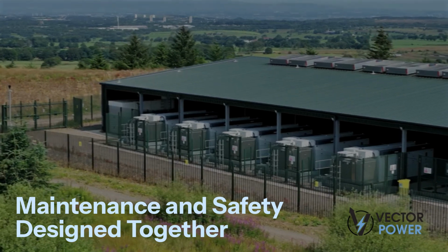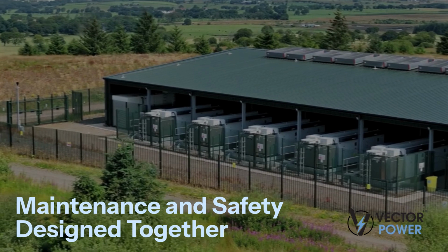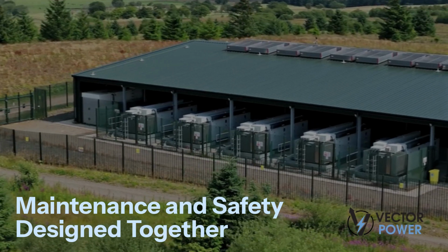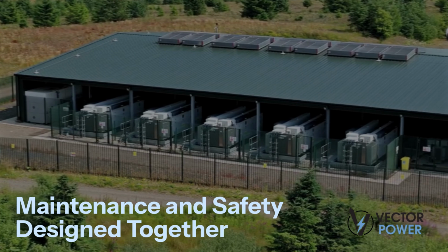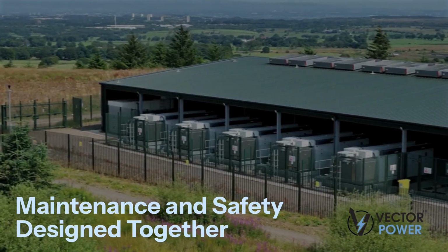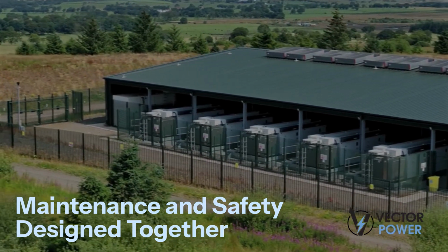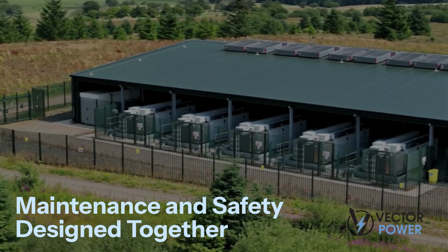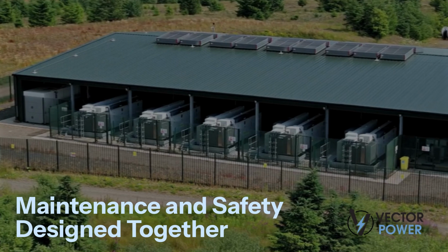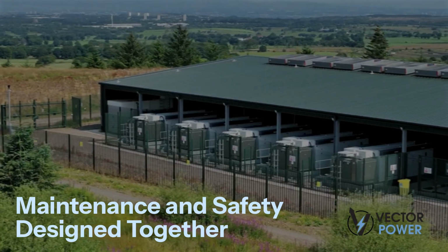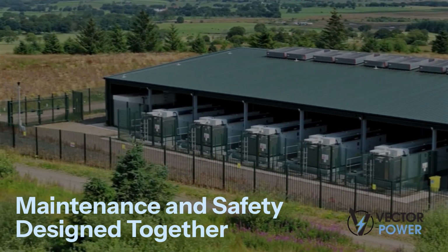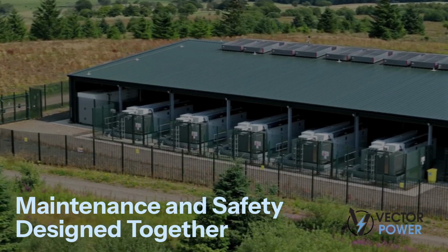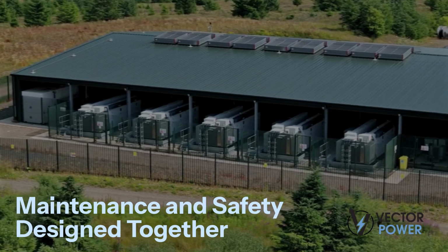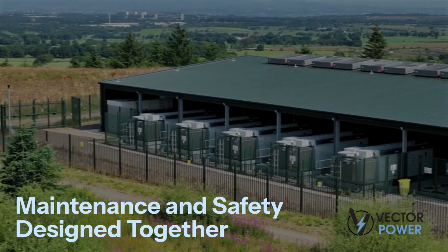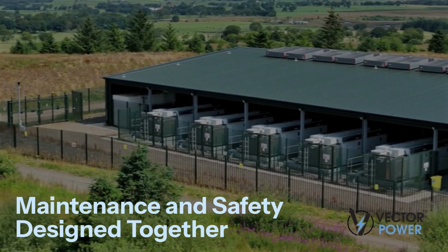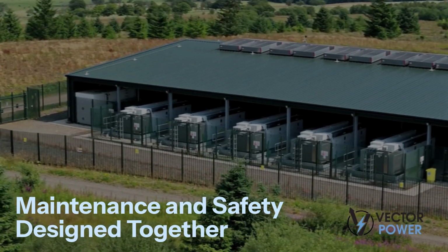Historically, battery maintenance was often treated as a narrow reliability function, for example, keep the UPS batteries alive. In modern battery energy storage systems, maintenance and safety are inseparable. Poor maintenance, such as disabled fans, loose terminations, and outdated firmware, escalates safety risk. Inadequate safety controls, like missing lockout tagout or no gas detection, expose workers during routine maintenance. Changes made during repairs can inadvertently break system level safety certification, for example, UL 9540 listing. It is recommended that energy storage systems be treated as safety critical electrical equipment, subject to the same rigor applied to switchgear, substations, and process safety systems.